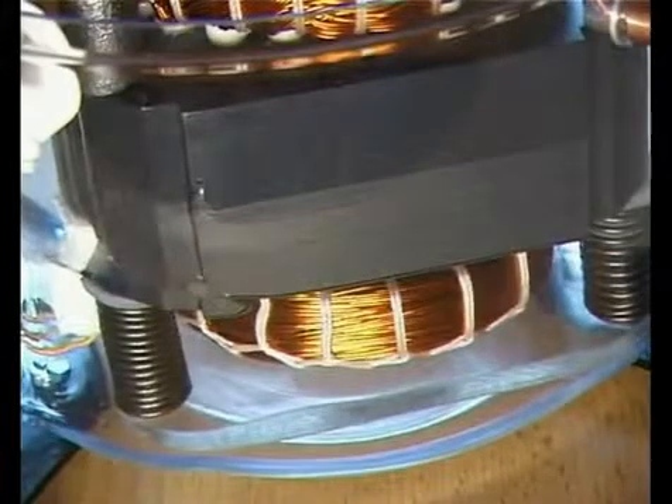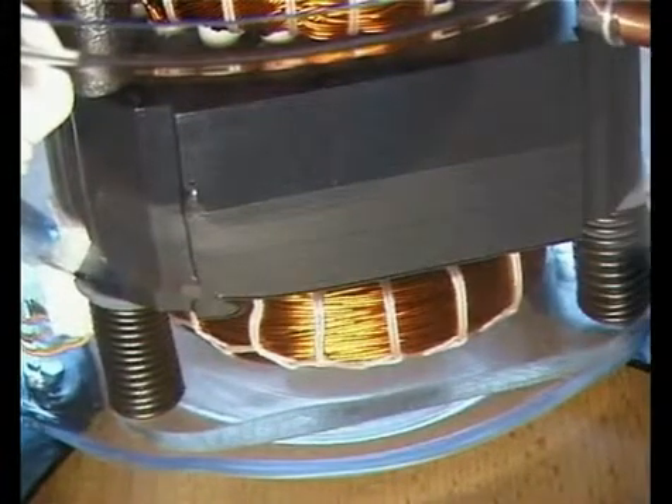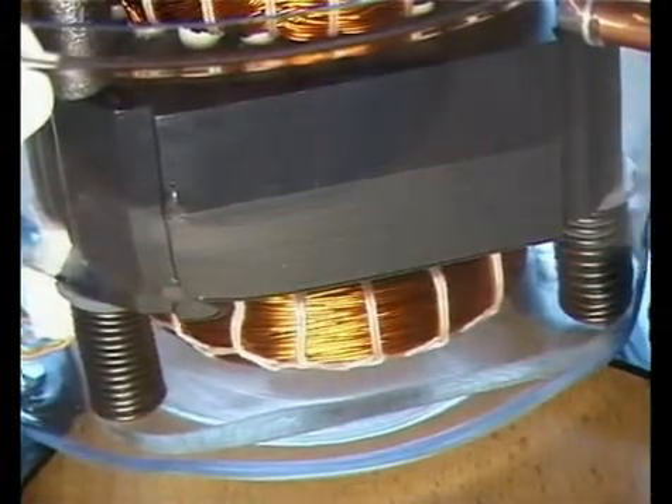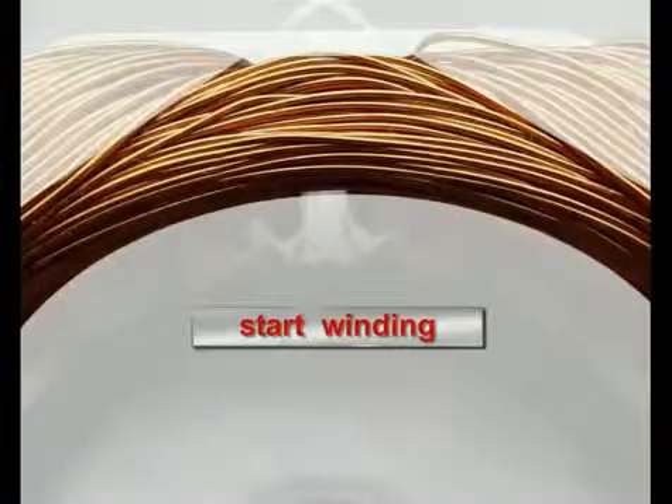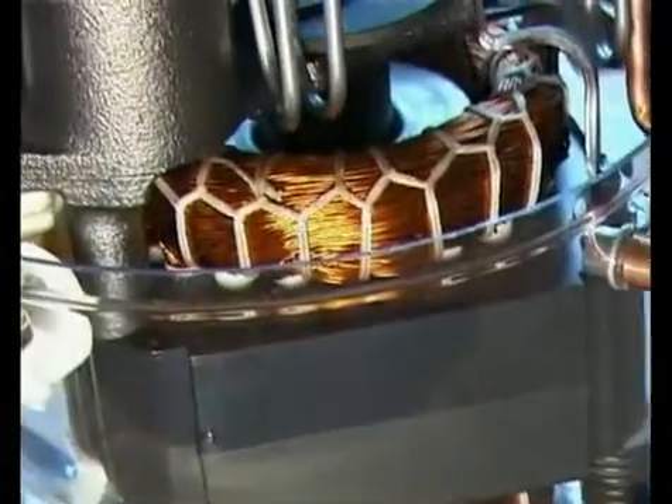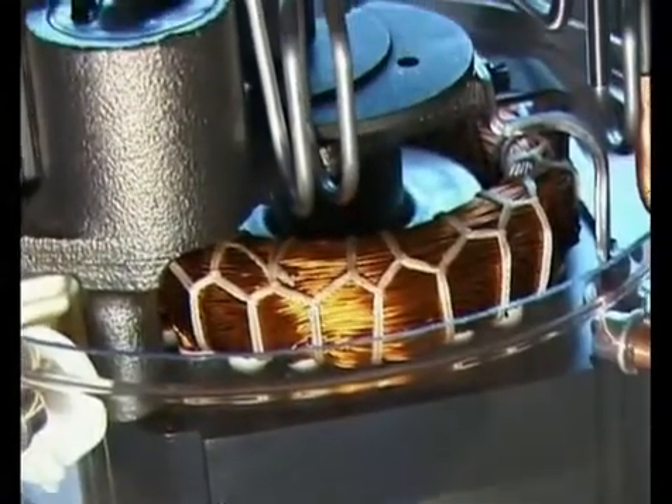The stator consists of a stator stack which is welded together out of sheet metals and two windings of enameled copper wires: a start winding and a main winding. The windings are protected against the loosening of individual wires to avoid damage.